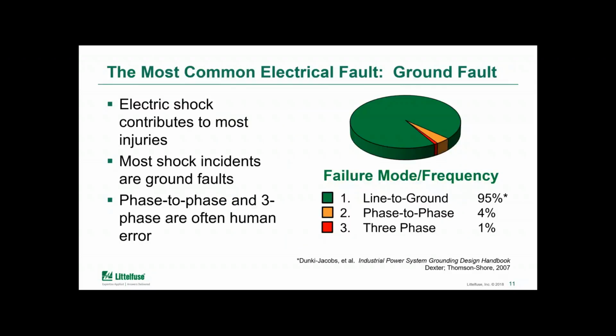So when we talk about a single line diagram, one of the pieces that, of course, would be referenced there is the grounding system, the grounding method. Now, most electrical faults, and here we reference some work by Dunki-Jacobs, where the number was 95% of electrical faults are ground faults. And as the majority of electrical injuries are shock related, and most shocks are ground faults, when you tie it together, it really comes to be a good place to start.